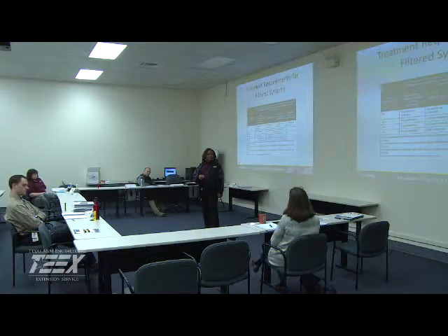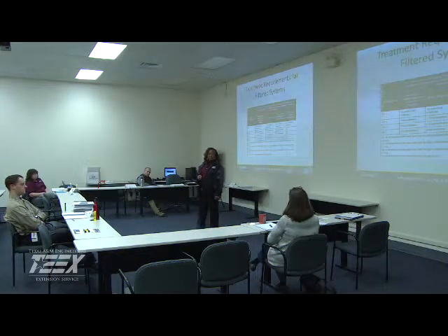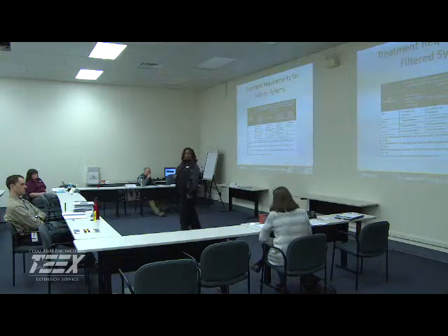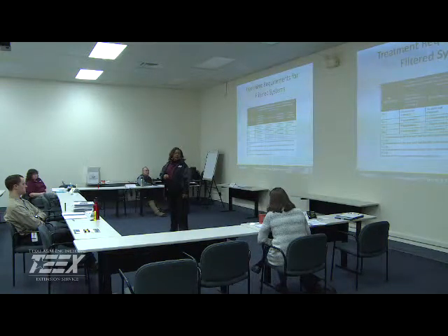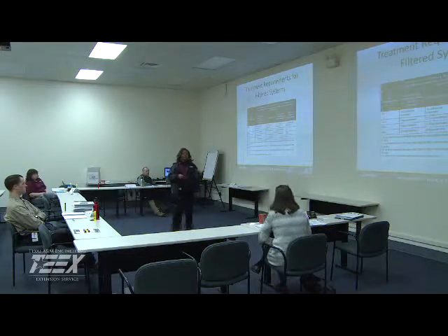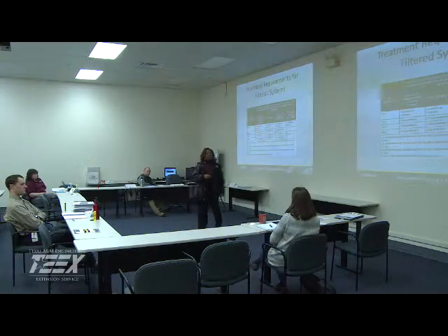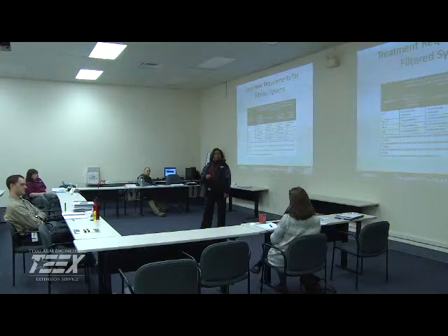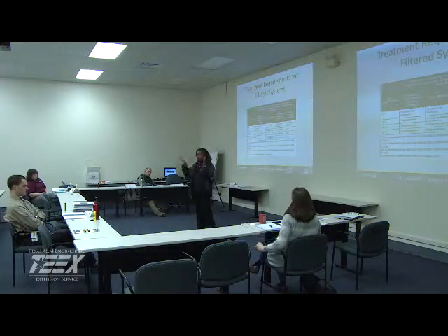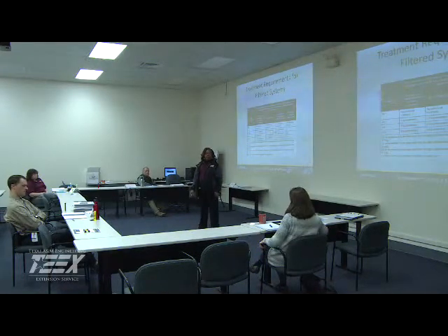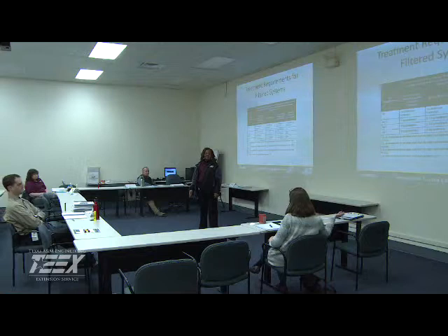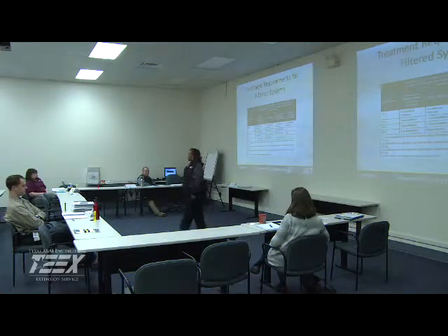half log, they went to individual filter turbidities at point, was it 0.125? 0.15? 0.15, yes. 0.15 at their individual filters. So they actually didn't change any treatment, but because of the source water protection, more or less. And I think Delaware's like number 1 in this sort of scenario of having a source water protection program approved for the credits.